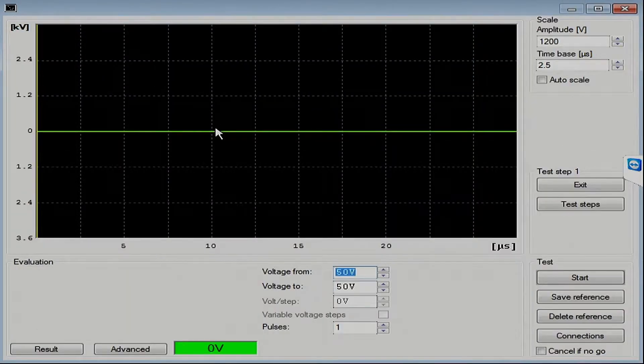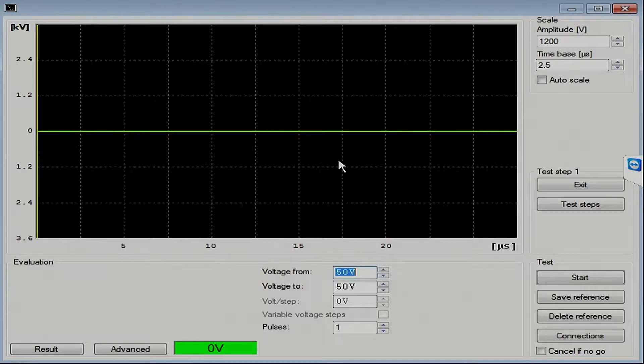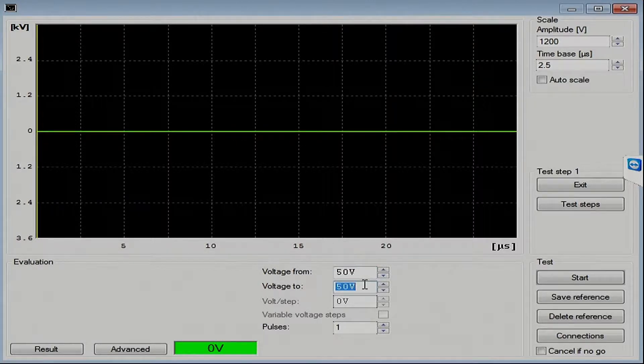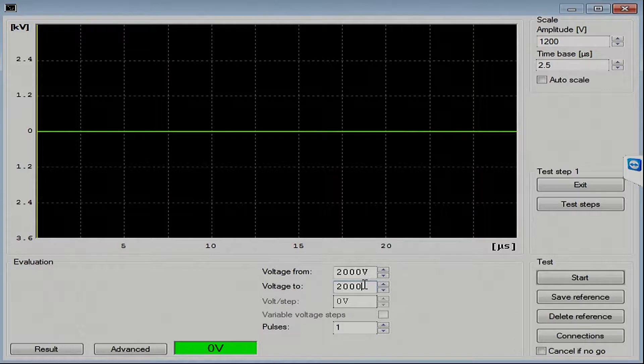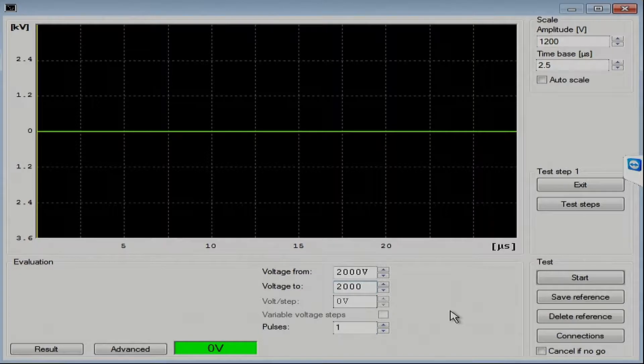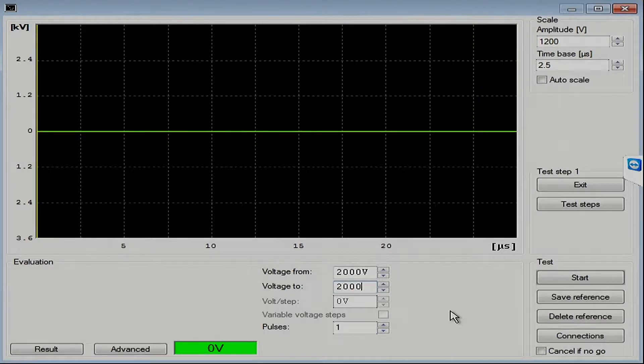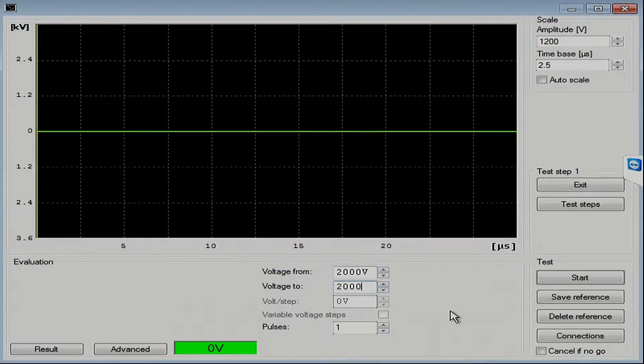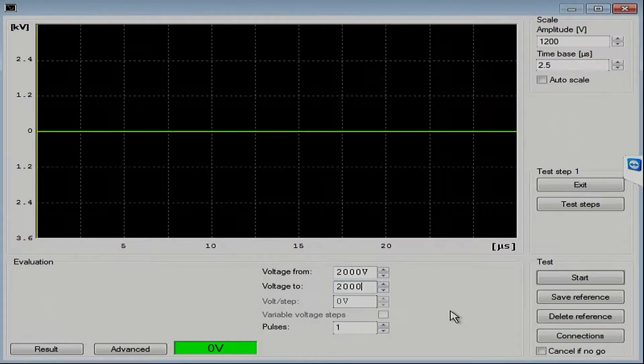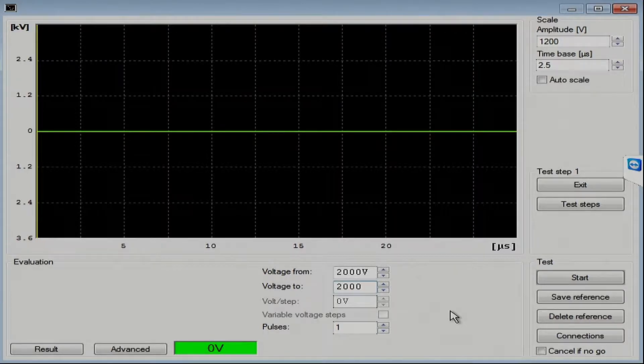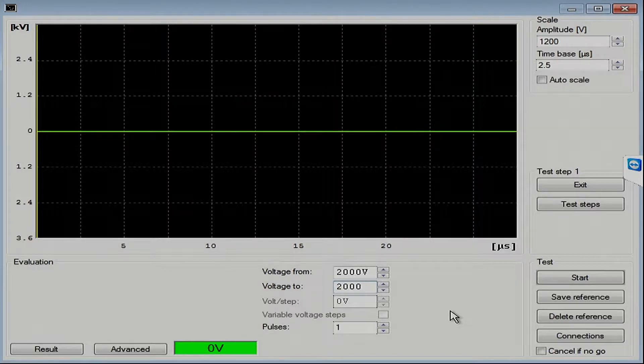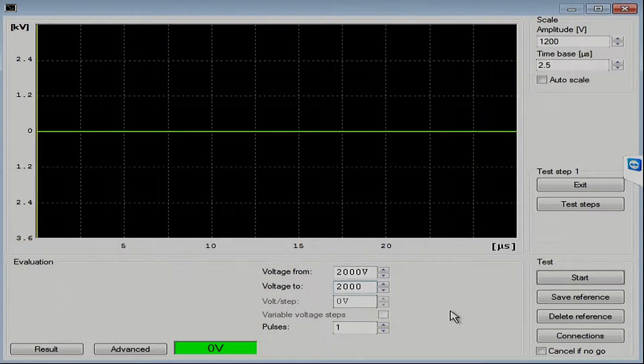Now, what brings up next is the surge test setup screen. I'm just going to go to 2,000 volts, and I'll tell you why. When we do a comparison test, we really don't need to ramp up from a low voltage to a high voltage. What matters is the waveform at the final voltage, or at 2,000 volts in this case, between phase A and B, B and C, and C and A. There's no need to start at a low value and ramp up.